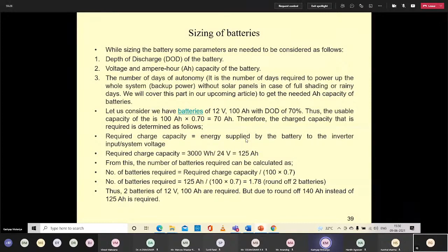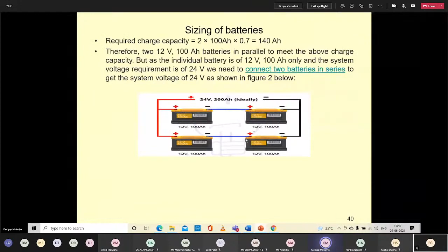This way, the desired capacity of your battery can be dealt with for a solar PV charging station, whether it is a domestic load or you go for a level 1, level 2 or the next charging design. So this equation is formed as per the previous slide. Step by step, what did we actually do? We have given the DOD, we have given the voltage rating of the panel, and from that we divided the required charge capacity by the nominal voltage and by the DOD.